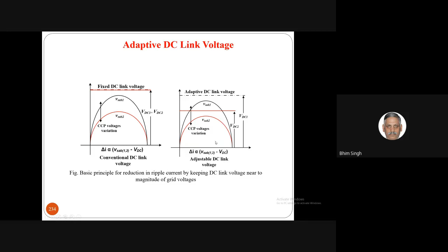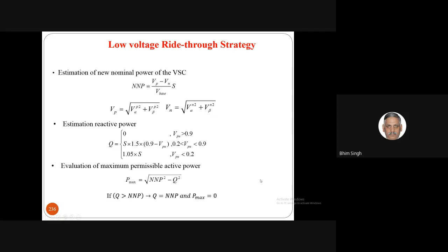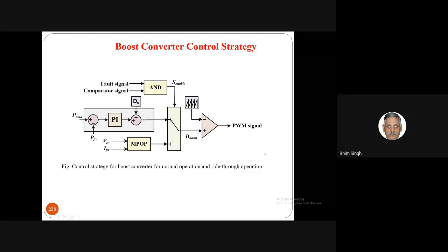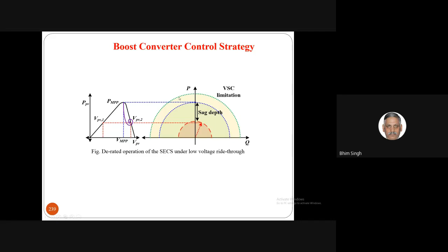There was a reduction because we are able to take adaptive DC link voltage during voltage variations and modify the control accordingly, so losses are reduced and we are able to maintain low voltage ride through, following the modifications given in the standard, and keep the inverter operating successfully under low voltage ride through problems. We also modified the control of the boost converter to take care of low voltage situations.